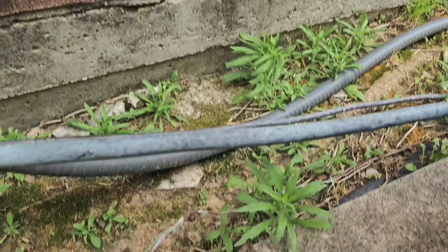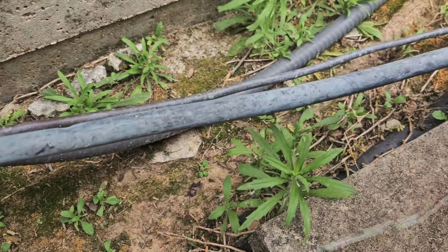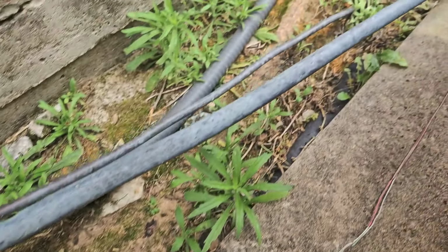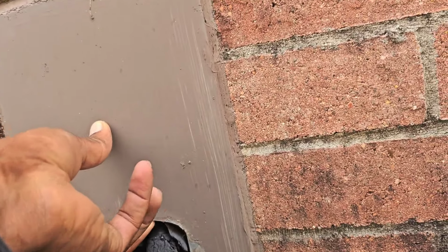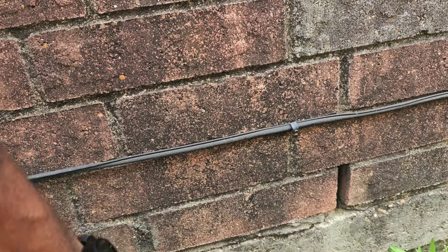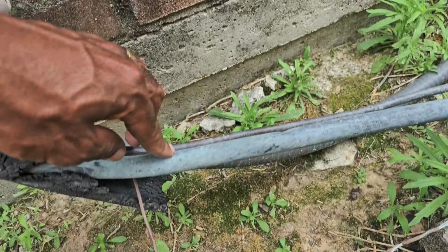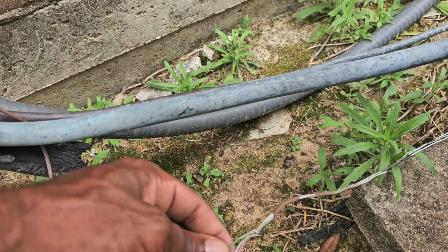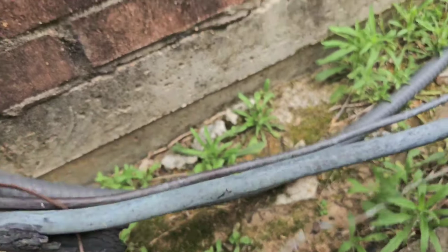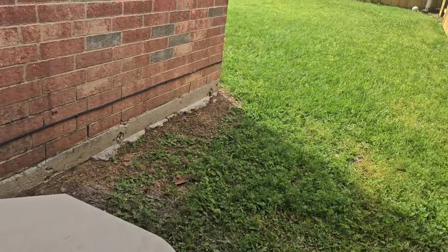I'll show you. Okay. All right. You know they look old, though. Like I said, it seems like a rodent problem up there, too. But look, might be the problem right here. Might not even be the contactor. Even if this wire touched that copper right here, it's gonna do it. But we know for sure this probably touching each other. I'm gonna open this contactor up.